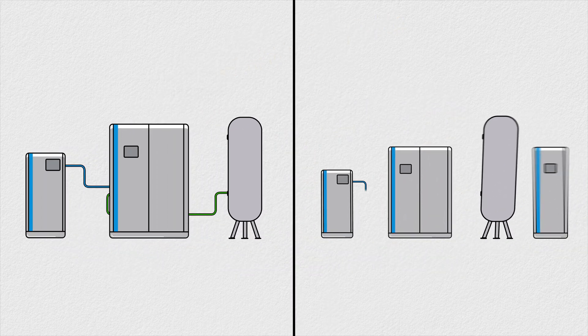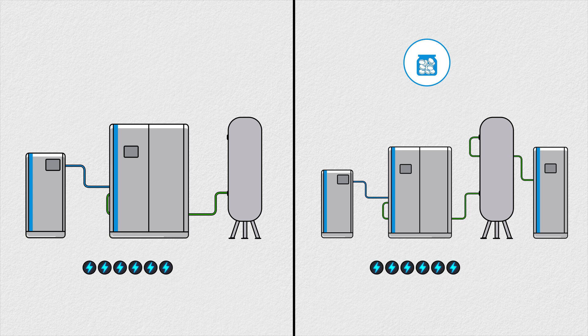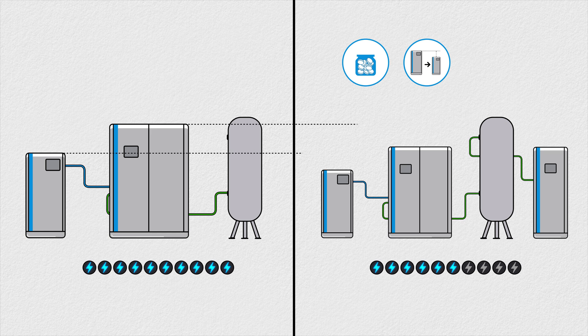However, a two-stage process with a purifier is often more cost-efficient as the system's compressor uses a lot less energy. The compressor and generator can also be sized smaller.